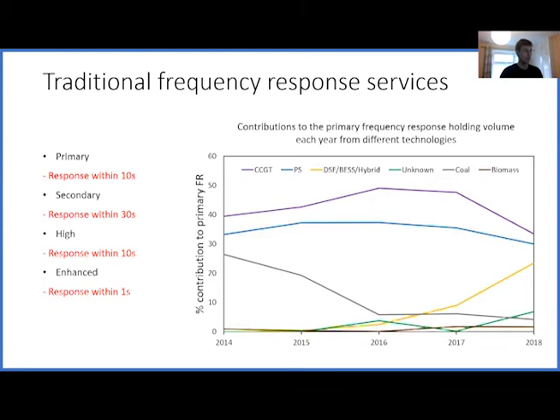There's this newer product, which I've still classed as a traditional frequency response service because it's been around since about 2017. It's enhanced frequency response. There's about 200 megawatts in Great Britain, provided by batteries, and it has to respond within 1 second, and it's symmetric, so it responds when the frequency is low and high.